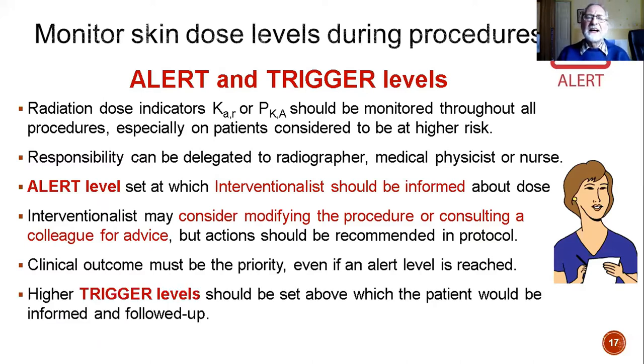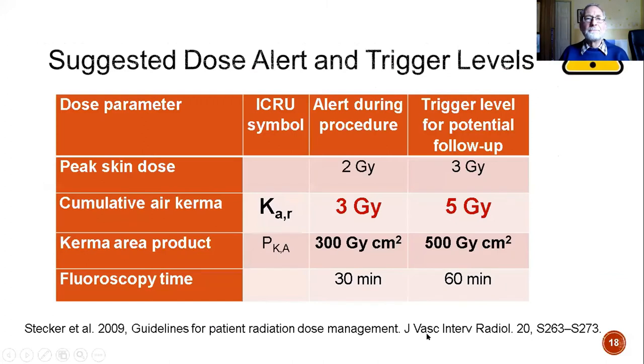Then also set a higher level, what we call a trigger level. This should be above, and any patient receiving above that should be informed and then followed up after the procedure. Suggested dose and trigger levels are: cumulative air kerma, 3 gray for the alert level and 5 gray for the trigger level. But values in terms of kerma area product are also suggested, and in peak skin dose.